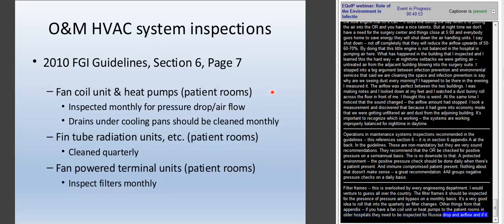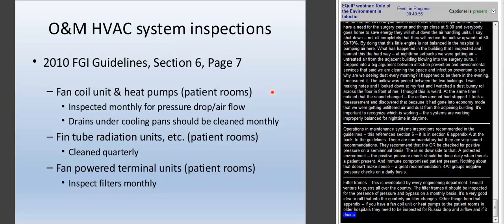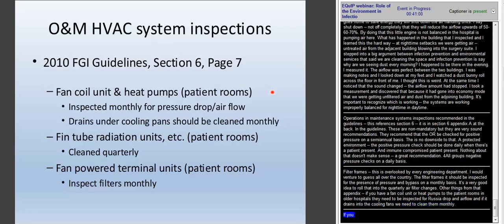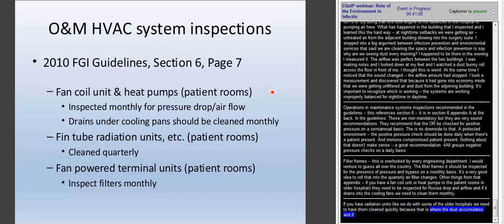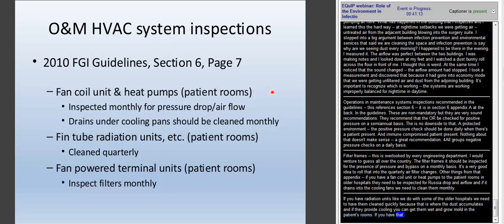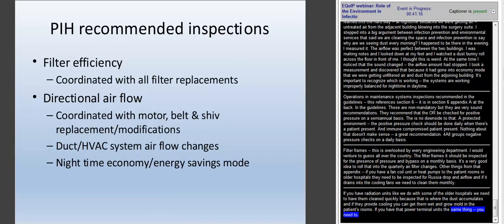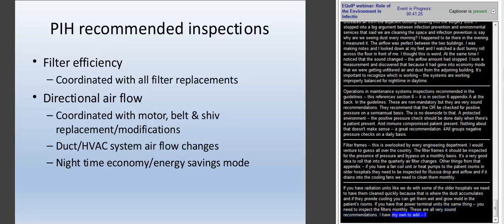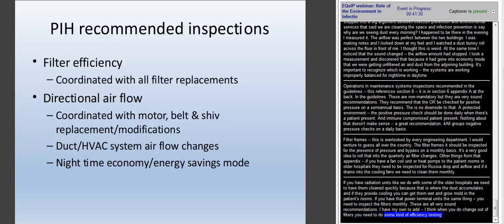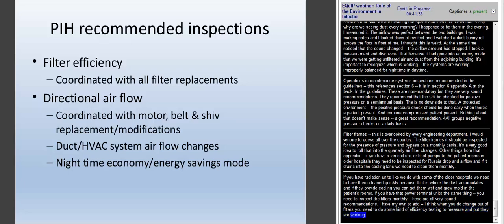If you have fin tube radiation units, like we do in some of our older hospitals, you need to have them cleaned quarterly because that's where dust will accumulate, and if they provide cooling, you can get them wet and you can grow mold in patients' rooms. And then if you have fan power terminal units, the same thing. You need to inspect the filters monthly. These are all very, very sound recommendations. And I have my own to add: I think that when you do change out all filter replacements, you need to do some kind of filter efficiency testing to either measure and prove that they're working properly, or secondly, do that light inspection to make sure there's no visual bypass.